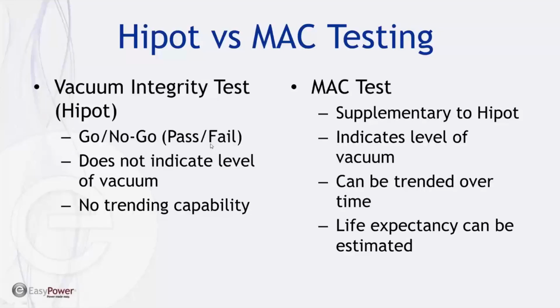The only problem with vacuum integrity, again, is that it doesn't indicate the level of vacuum inside. So you could be days away from failure and still get a passing result. Also, it's not trendable over time, so you don't see a degradation in these results as the vacuum degrades. Whereas with the MAC test, it's supplementary to the high pot test. So it actually gives you a data point that you can put on this Paschen curve and see that data point move over time as you retest the vacuum interrupter during your normal maintenance cycles.